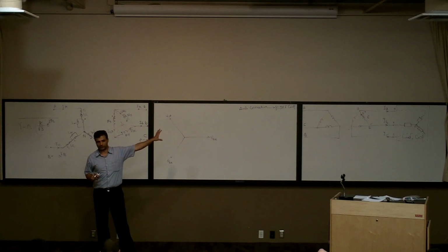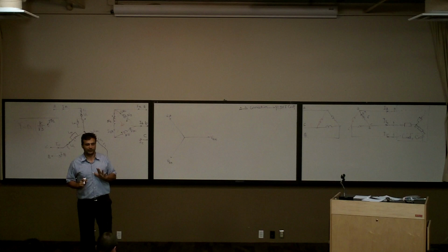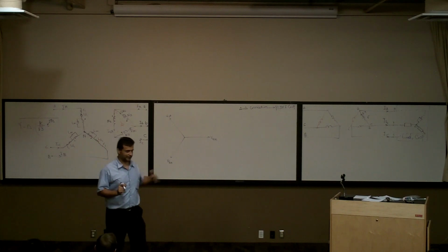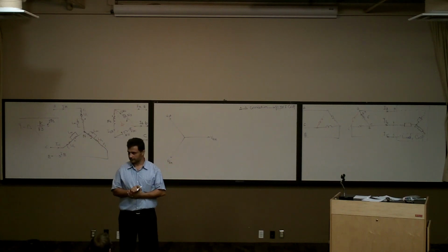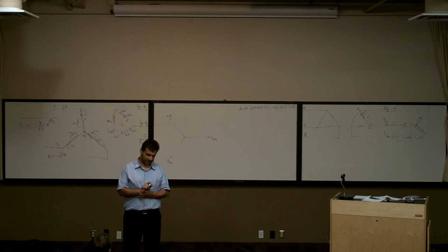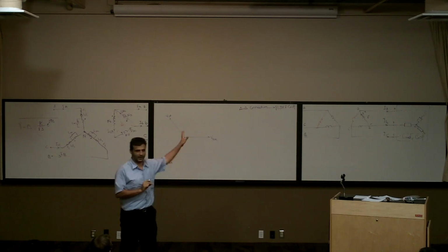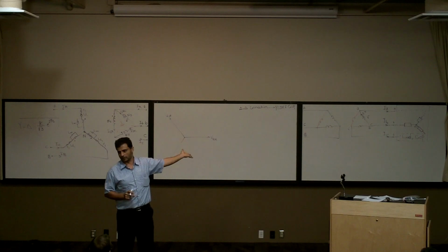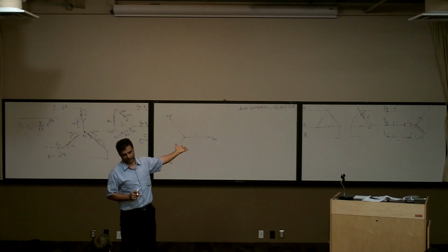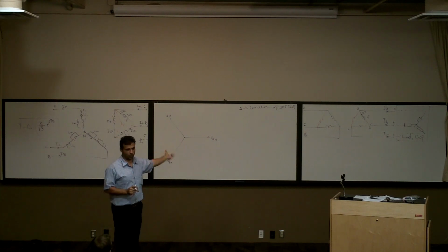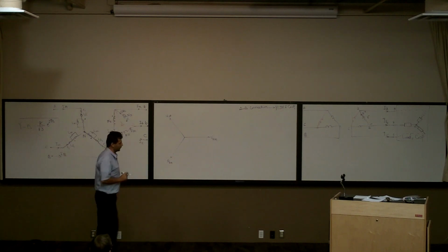Originally, when I had the 3-phase transformers, I'm going to ask you this question. Let's say it was 300 kilowatt. What's your guess when I have 2 windings? 200 kilowatt. It looks like a very reasonable guess, but it's not correct. We'll go through why. But a very good guess. Myself also, the first guess would be, okay, I had 3, 1 is gone, so now it's going to be 2/3, right? 200 kilowatt. But let's go through the equation to see why it is not.